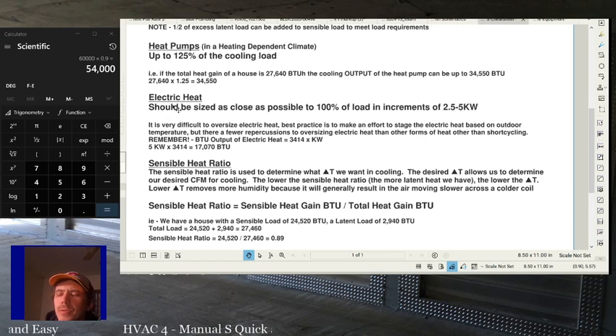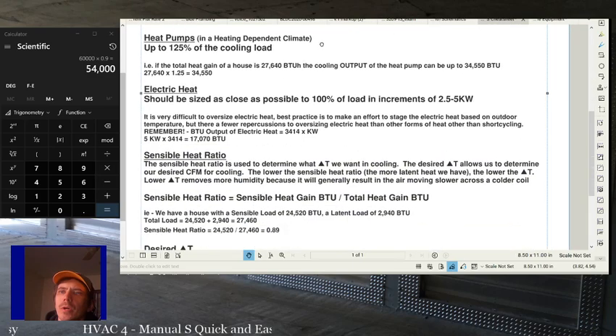Electric heat. So electric heat is pretty simple. You size it as close as you can, as close to 100% of the load as possible without going under. There's really no reason to undersize electric heat, and you're usually going to be in increments of 2.5, 3, or 5 kW. So whatever meets the load, okay? I didn't put an, well, let's go through this and then I'll probably put another example here real quick. All right, so it's very difficult to oversize electric heat, like I just said.